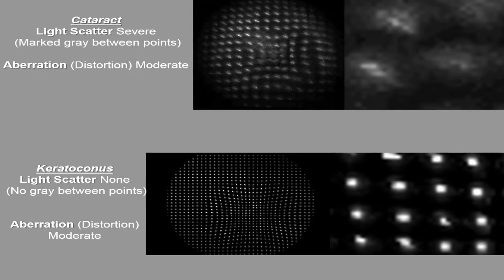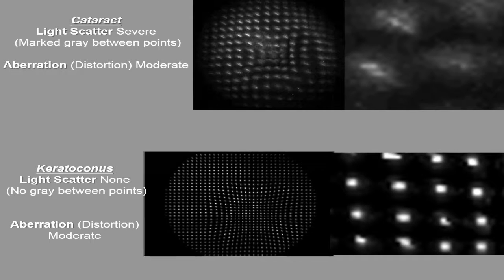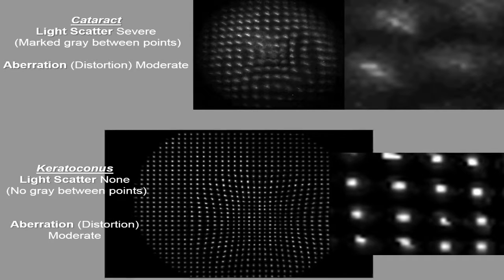One way to understand the difference between wavefront and light scatter is to picture the device that measures wavefront — the one that shows little dots in an array. We have a grid of dots, and a wavefront analyzer takes a picture of those dots through the optical system. If those dots are not exactly as they were in the original grid — if they're compressed, distorted, or moved — that's what we call wavefront, and it is a measure of optical quality. But light scatter is something else.